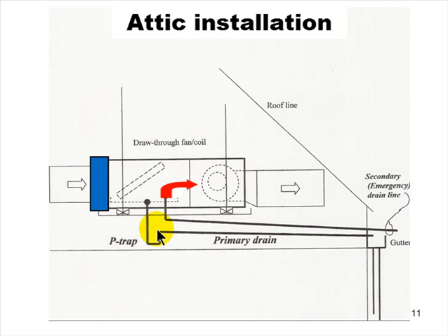In fact, your trap always has to be twice as deep as the possible static pressure that the fan can develop. So if you've got a fan that can develop an inch and a half, this trap has to be at least 3 inches deep.